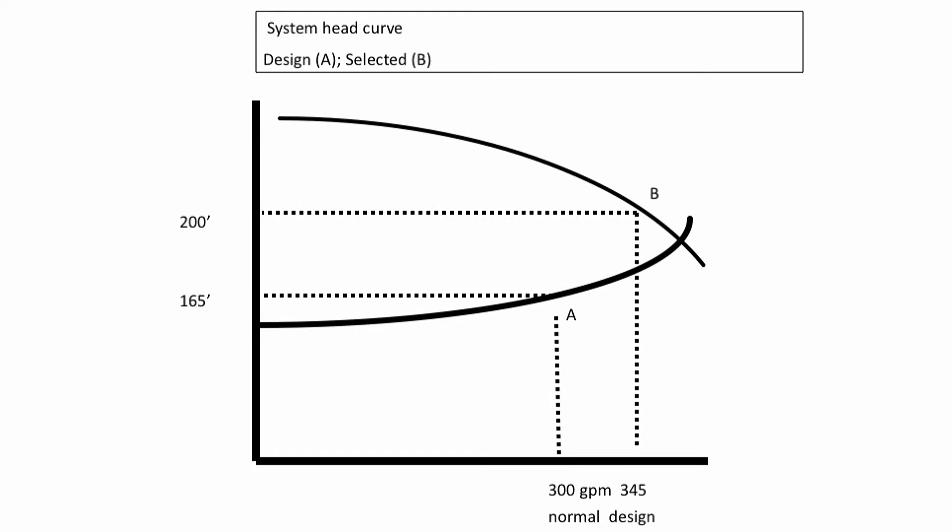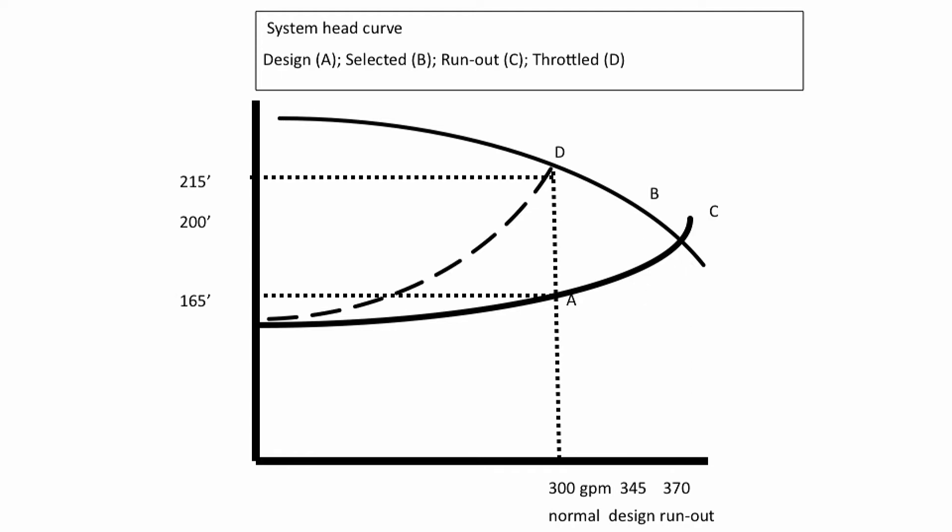You pick a pump for this service. If your original calculations are correct, the pump will now run out to 370 GPM, point C. In order to have a flow of 300 GPM, you must throttle the control valve to add head to run the pump back on the curve to this point D.